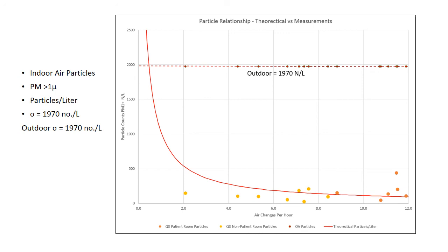We're statistically bouncing around that asymptotic portion of the curve, but we have every reason to believe that we can drop these air change rates down to 2 air changes or below, and still have very, very good air quality within the spaces. Obviously, it'll vary by space, but we have all those sensors in place by space. So that's the data.